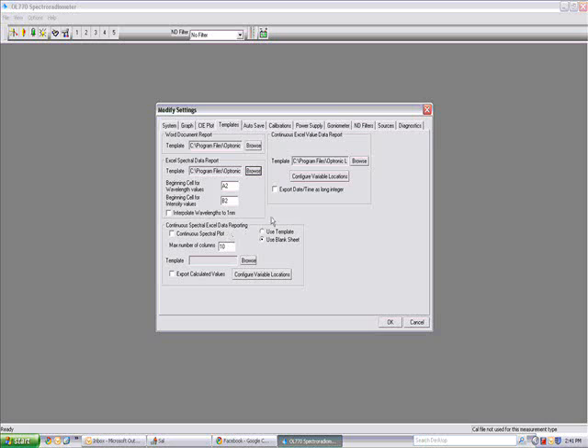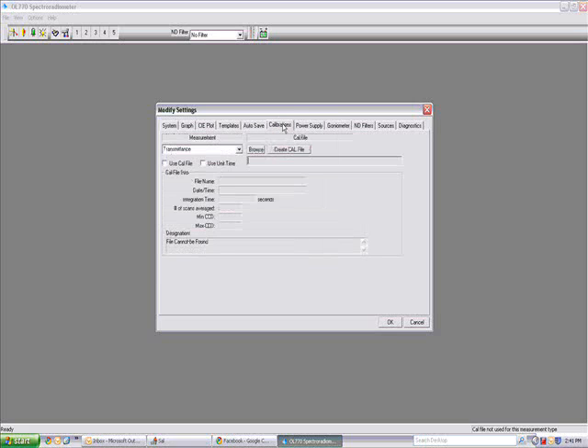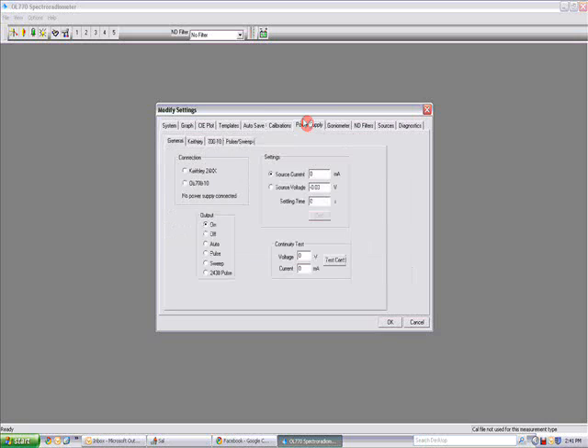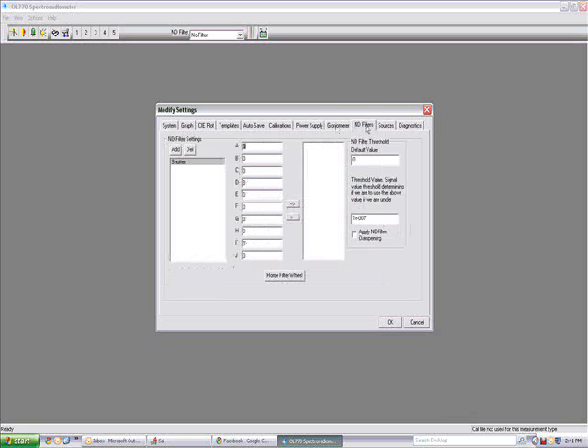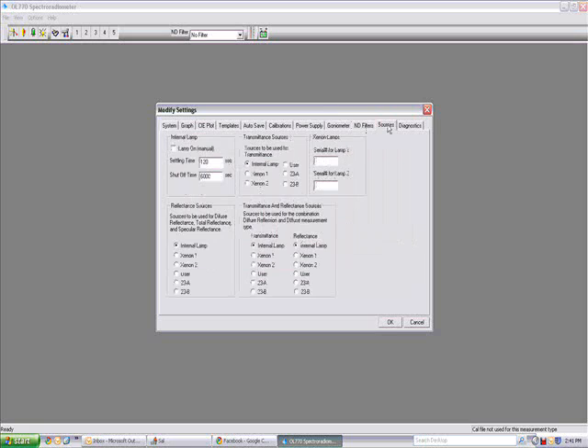Software features include active zoom view CIE diagram with customizable lighting requirement boundaries, the ability to see all pass-fail conditions for all lighting requirements in a specification simultaneously, fast access to all NVIS data even while the instrument is continuously measuring, and editable NVIS requirements to alter current specifications or create new ones.